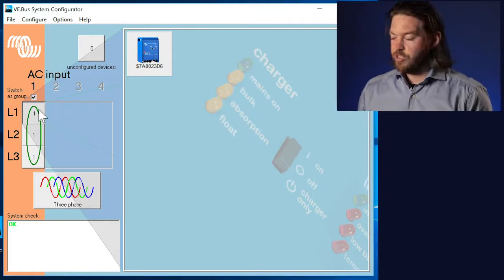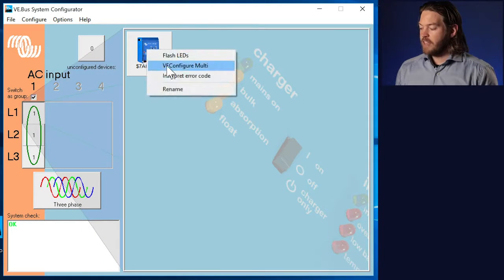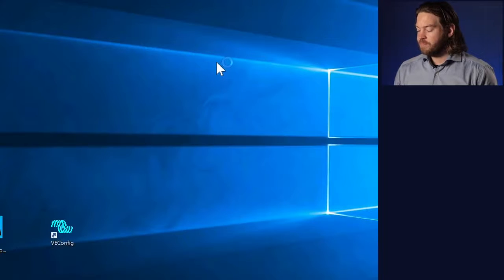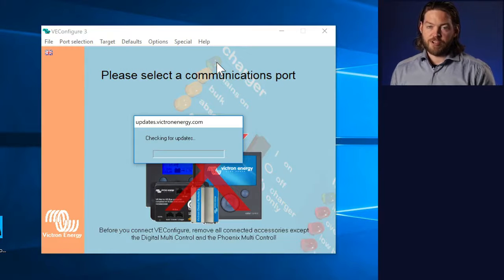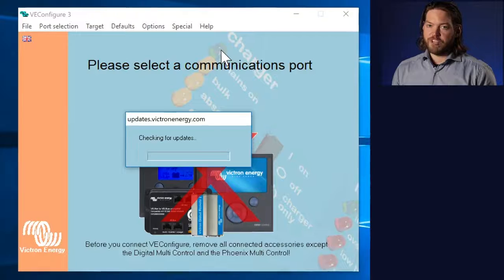Now I can't just open up VEConfigure as I normally do. I need to be able to open up VEConfigure and assign it to a particular unit. To do this, I select the phase that I want to use, right click on the multi, and then select VEConfigure multi. This will close the Bus System Configurator tool and open up VEConfigure. It's important to make sure that the assistants especially are loaded on each unit individually. All 3 units need to have the assistants loaded, especially the ESS assistant for this example, but other settings as well may need to be set to all 3 multis individually.